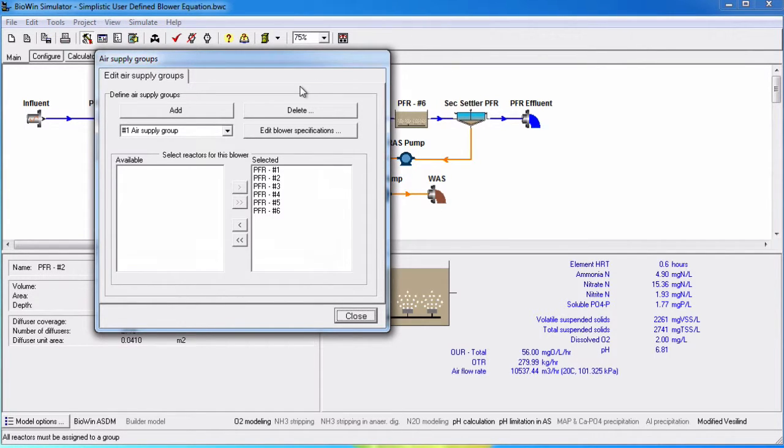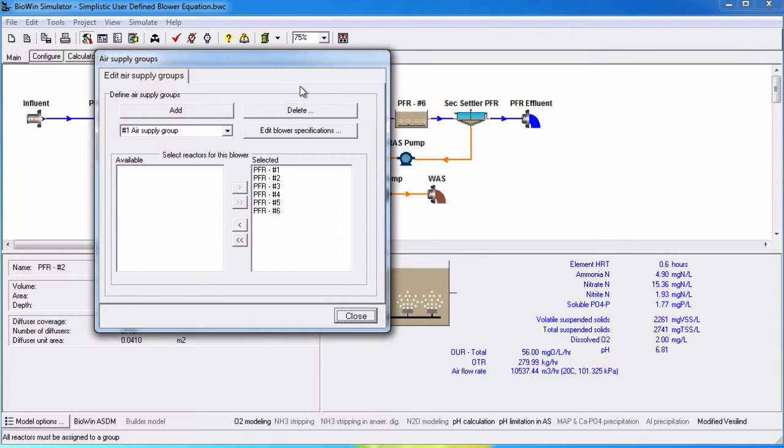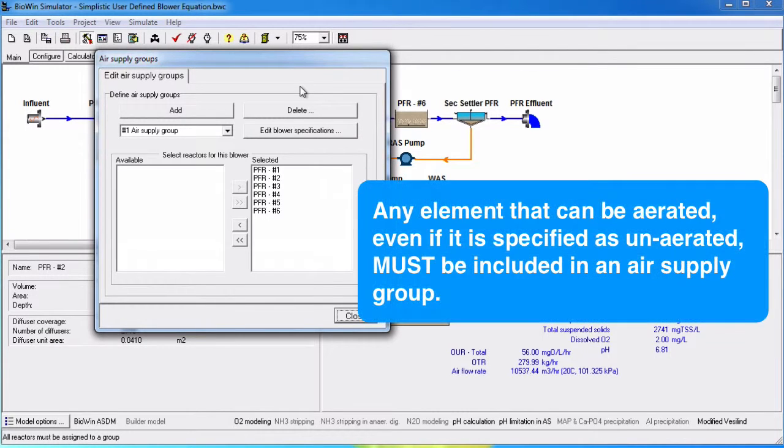Once a configuration is built, all of the elements that can be aerated, even elements that are specified as un-aerated, will be automatically added to an air supply group and will appear in the selected list. If a reactor remains un-aerated, it will not contribute to the power calculation of a blower group, but it still must be included in an air supply group.